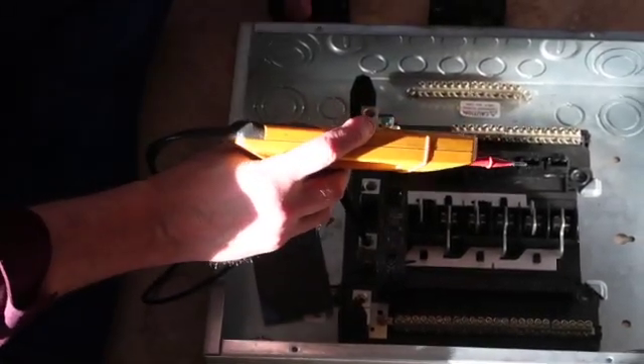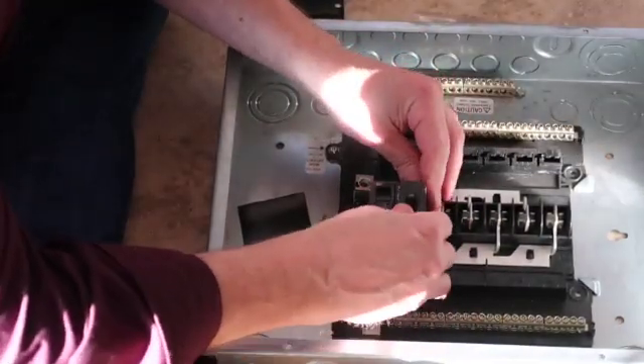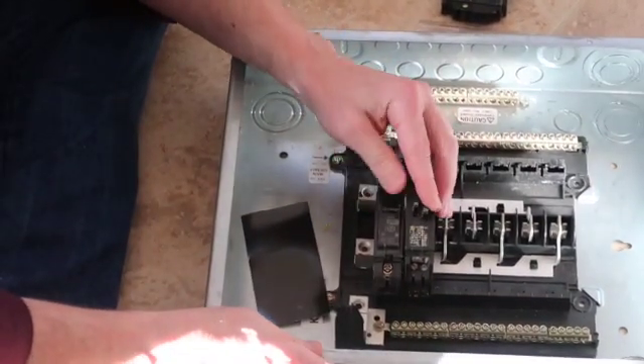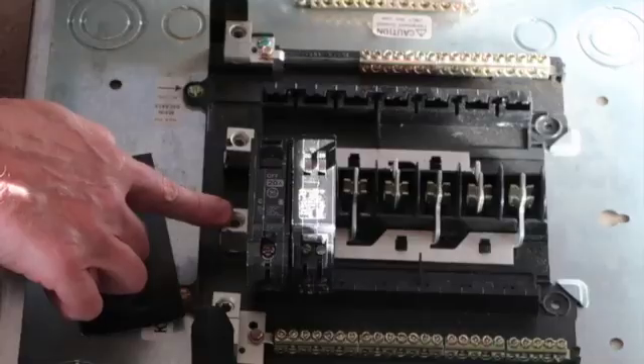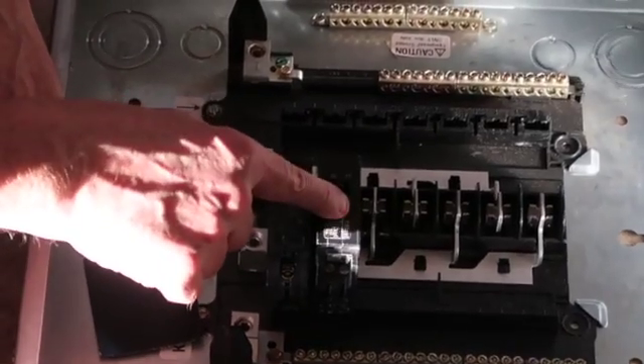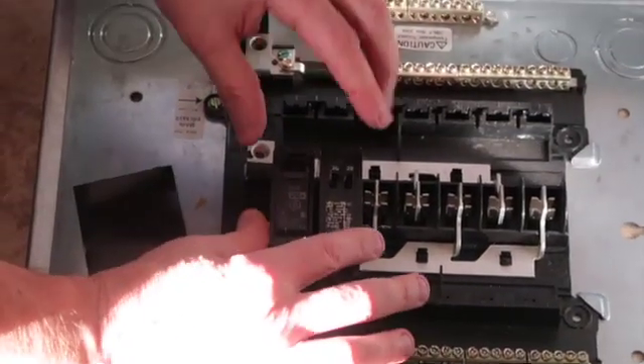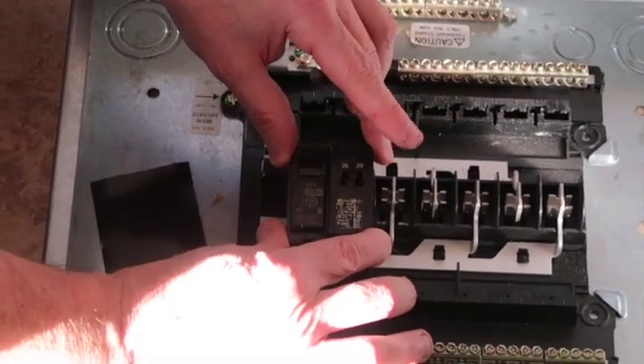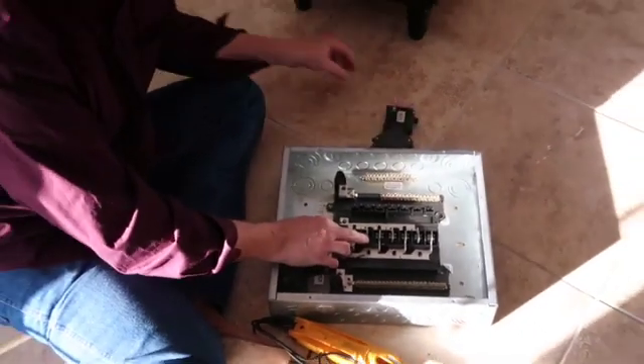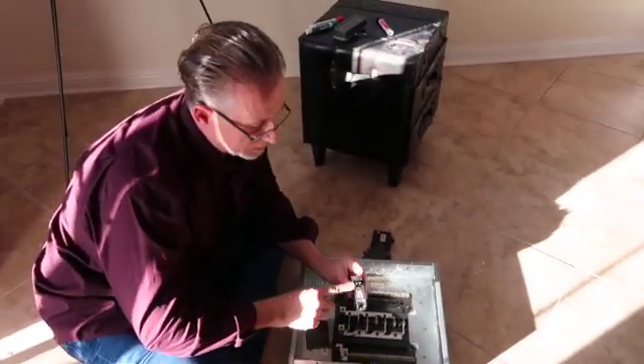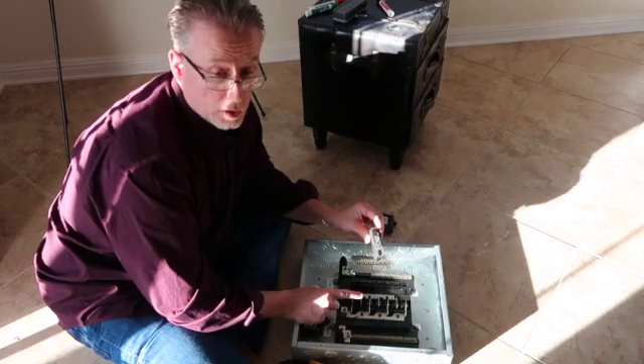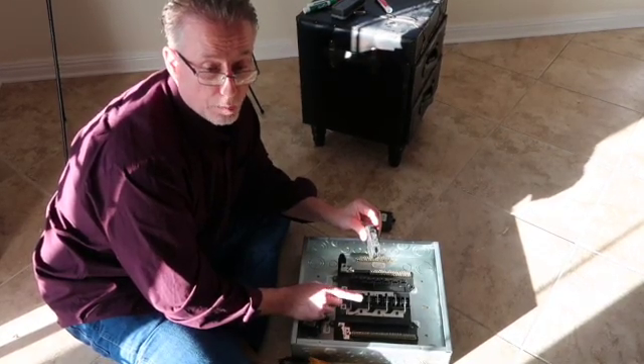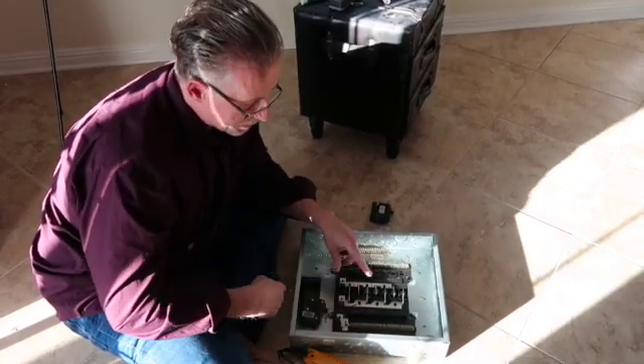And then if we had another one we would put another one. If this one were working we would put it in here. And this one here is just broken because I can't get it to reset. But basically this is how breakers would go. So this right here would go to this hot, this one here goes to this hot. If I had another one here it would go to this hot. Every other one equals this. So if you had two wires coming out of here you can get what they call a 240 breaker and put a 240 breaker here. The reason why you want 240 together is if something happens, my code says they have to be tied together so that when one hot leg trips the other one will trip with it, so that you won't think it's off when it's really just one hot leg is open or shorted or whatever. So you have to tie them together, but this is basically how it works.